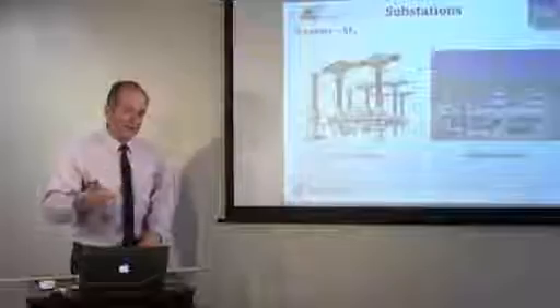That arc that's in there, the more current, the bigger the arc. If you have full load, you could have a tremendous arc, but if you put oil in there, the arc is reduced. If you put SF6 gas, the arc is greatly reduced, okay? So depending what you have in there, you could have vacuum, or air, like an air switch. It's like hardly any dielectric strength, but vacuum helps. Oil is better, and SF6 gas is better yet.